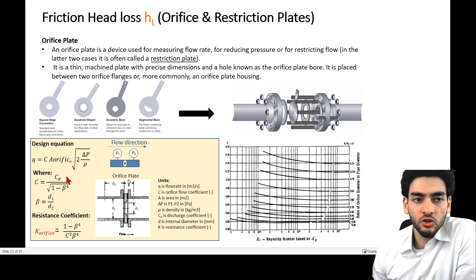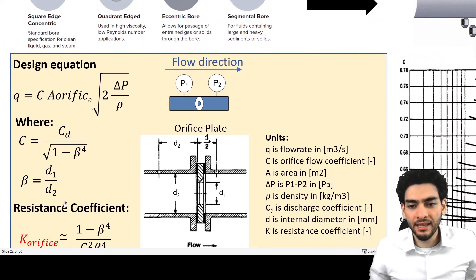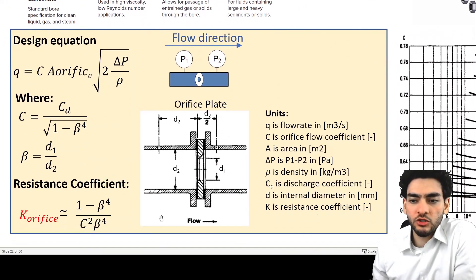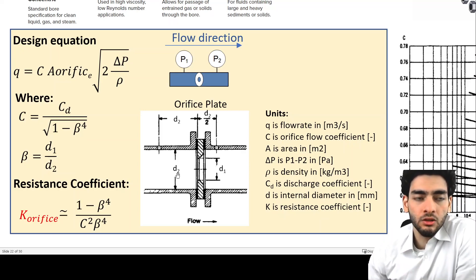You might be wondering what the discharge coefficient is and what beta is. Beta is the ratio of the diameter of the orifice divided by the diameter of the inner pipe that the orifice is installed in. The discharge coefficient is essentially the ratio of actual flow rate that passes through the orifice over the theoretical flow rate.